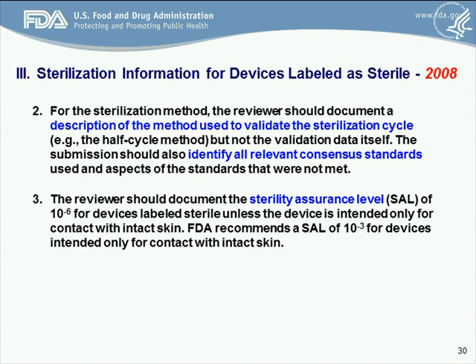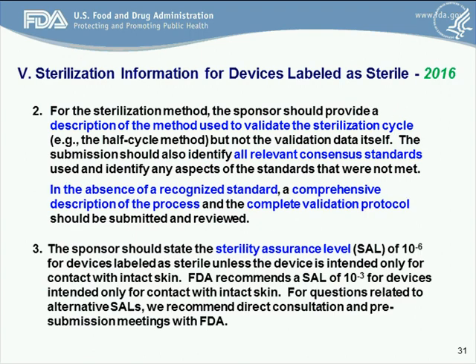Moving on to item number two — in the 2008 draft, we were looking for a description of the method used to validate the sterilization cycle, but not the validation data itself, and we asked you to identify all relevant consensus standards. In the 2016 final version, we're asking for a description of the method used to validate the sterilization cycle, not the validation data, but all relevant consensus standards, and in the absence of recognized standards, a comprehensive description of the process and a complete validation protocol. Item number three — we're looking for the sterility assurance level, and that really hasn't changed.